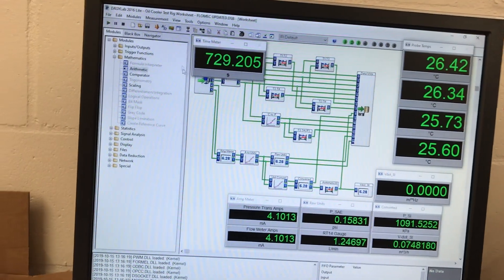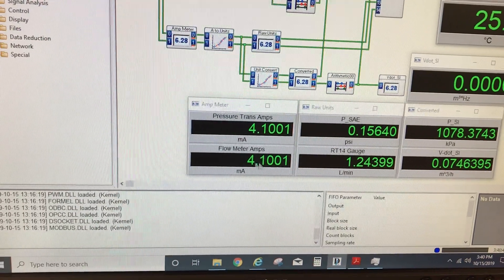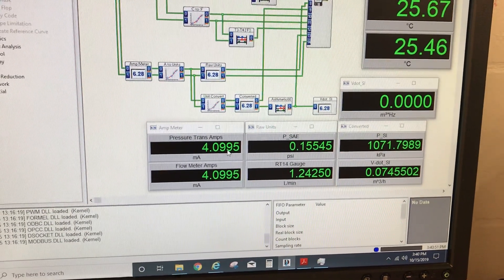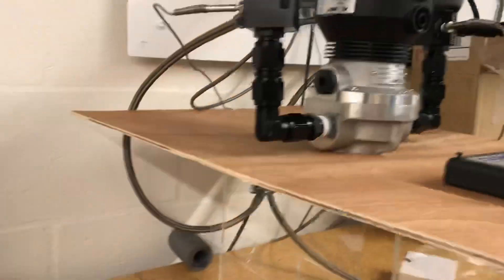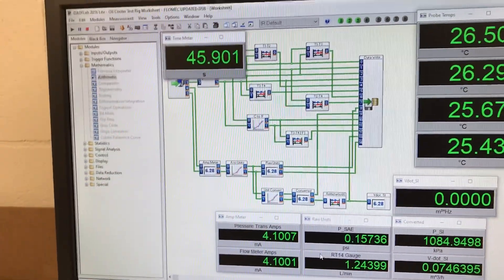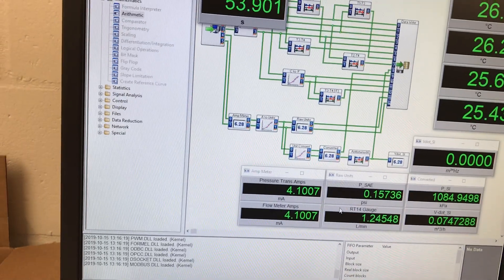Check out those amps — it's getting a little bit better now. Not really. The funny part is with these stray amps, adjustments are not doing anything. And then the most annoying part — if I were to change the zero, which I think I'm going to have to change the span, but if I was to do that on my pressure transducer, I can't even get rid of that crap right there.